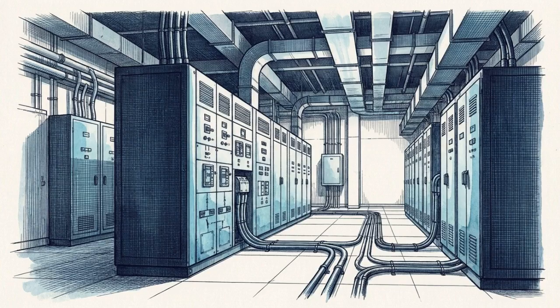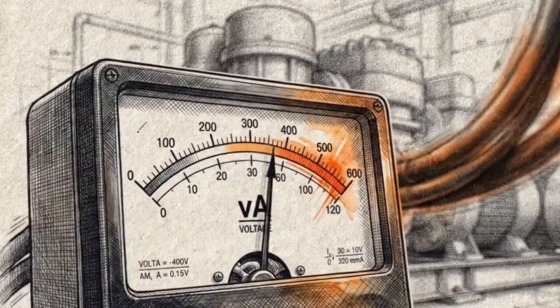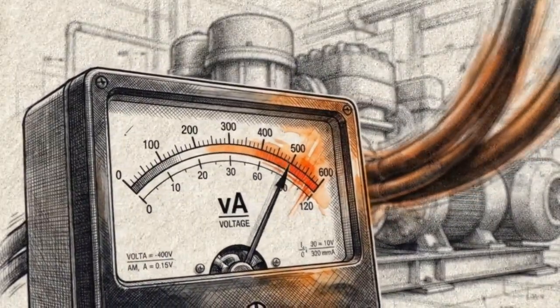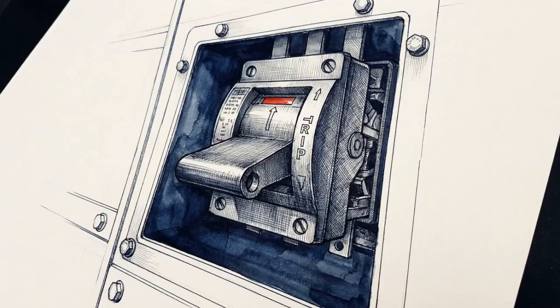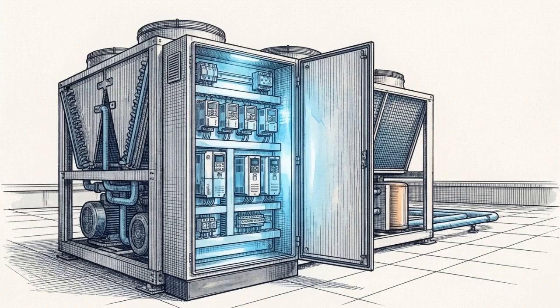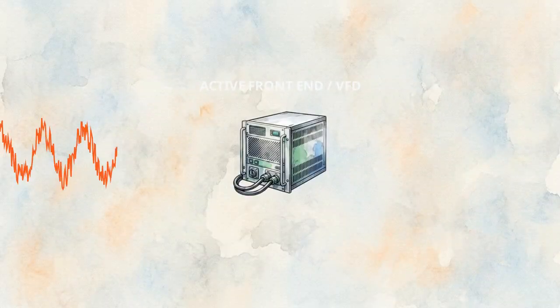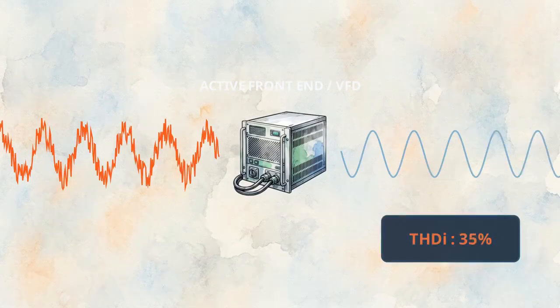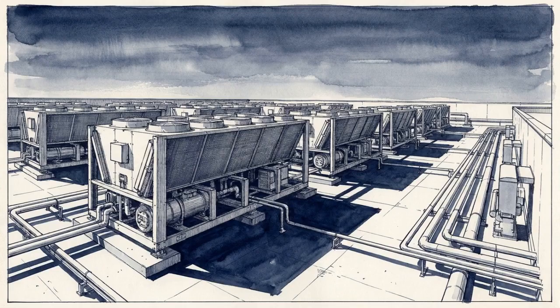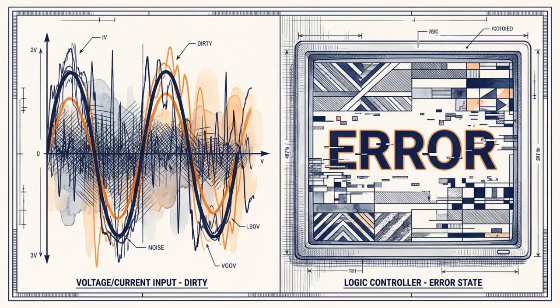Once the generators assume the load, a secondary electrical threat emerges. The massive power draw of chiller compressors attempting to restart creates severe harmonic distortion, which can cause premature breaker trips on the backup generators. To maintain generator stability, active front-end variable frequency drives are integrated directly into the chillers. These multi-pulse drives progressively filter the electrical draw, capping total harmonic distortion below 5%. Without this fiercely isolated and heavily conditioned electrical foundation, the massive chillers lack the clean power and retained logic memory required to even attempt a safe restart.